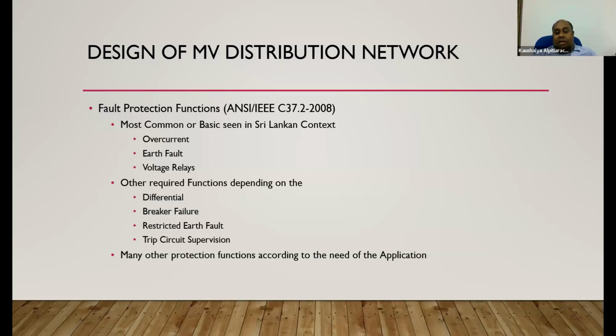And other required functions may be differential protection, breaker failure protection, earth fault protection, trip circuit supervision, and maybe some frequency related protections. And apart from that, depending on the application type, let's say it's an industrial application, you may need some other protection functions, maybe liquid starters and related protection functions, maybe for motor rotor protection and so on.